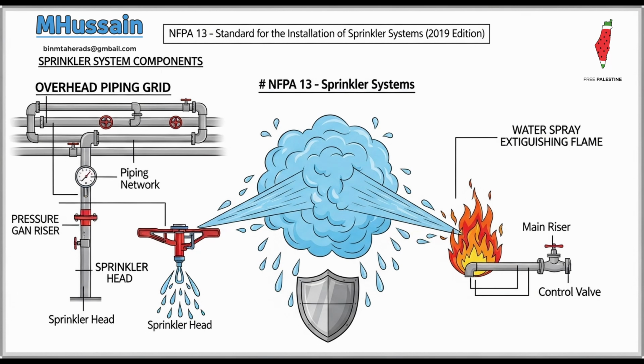And just briefly, on electrical rooms, these are often sources of debate because of the potential water damage risk. Yeah, they are. Sprinkler protection is generally required in electrical equipment rooms. That's the default. However, the rule does allow for omission if specific alternative safety requirements are met. This could mean installing gas-based extinguishing systems, or maybe if the room contains only certain types of fully encapsulated or non-liquid sealed equipment. The absolute key, though, is that the AHJ must approve whatever alternative protection scheme is proposed.